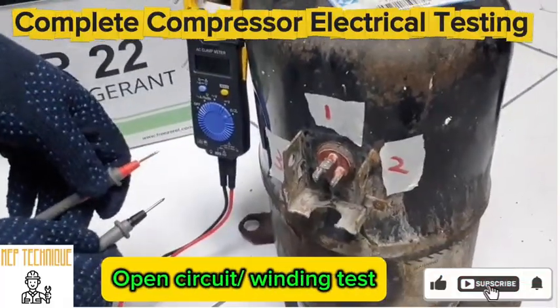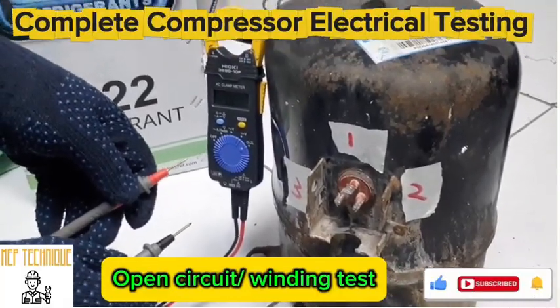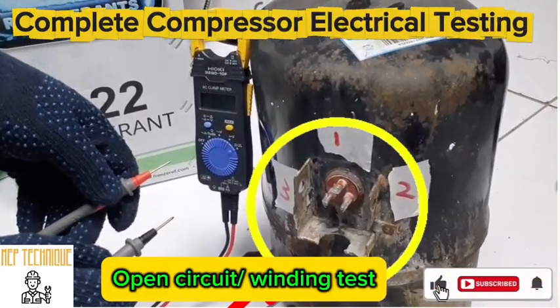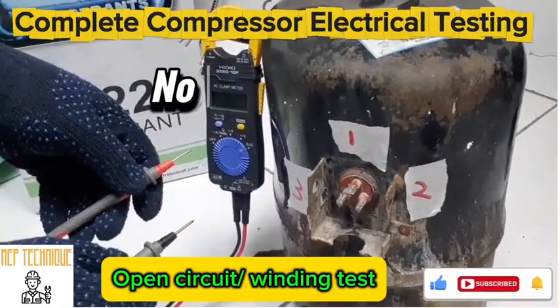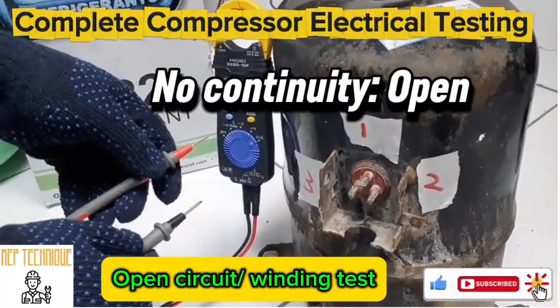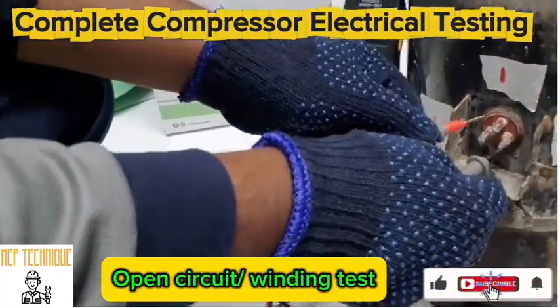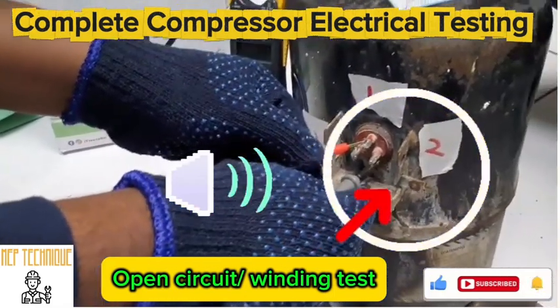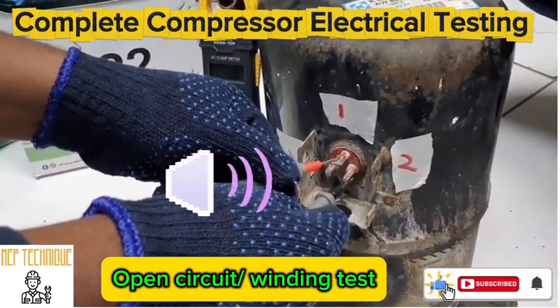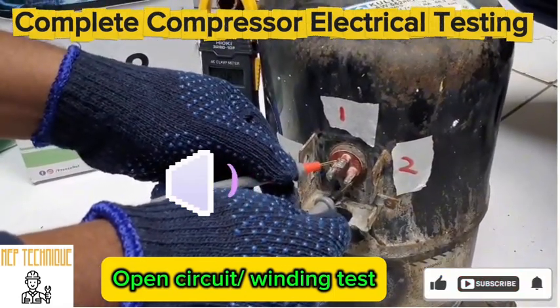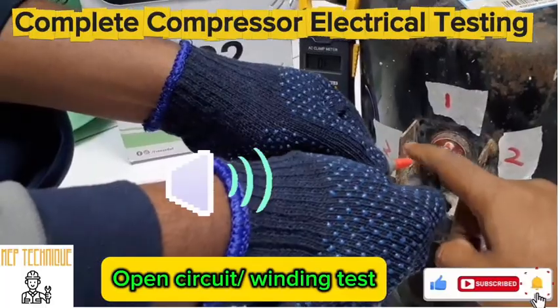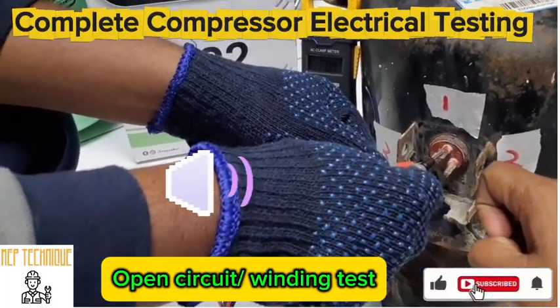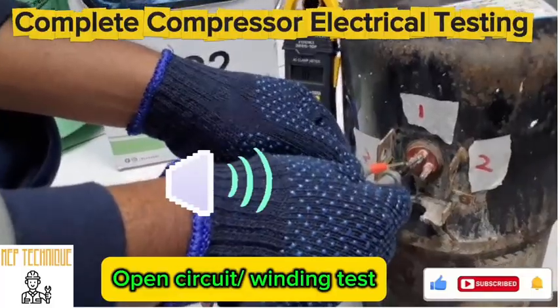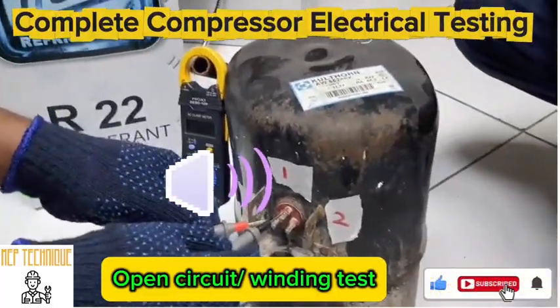First, we will do the open circuit test. You have to check the continuity between each terminal. If there is no continuity, that means your winding is open. Let's check 1, 2, 3. So there is continuity, which means there is no open winding.